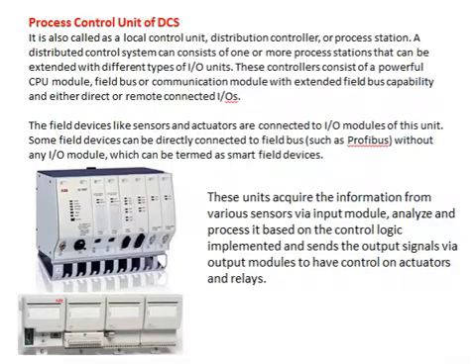Process control unit of DCS. It is also called a local control unit, distribution controller, or process station. A distributed control system can consist of one or more process stations that can be extended with different types of I/O units. These controllers consist of a powerful CPU module, a field bus or communication module with extended field bus capability, and either direct or remote connected I/Os. The field devices like sensors and actuators are connected to the I/O modules of this unit.